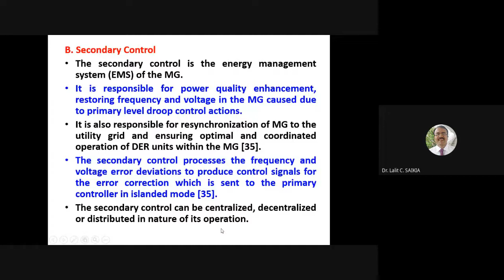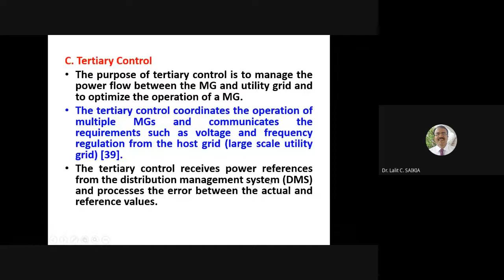Tertiary control's purpose is to manage the power flow between the microgrid and the utility grid - from microgrid to utility and utility to microgrid. Tertiary control coordinates the operation of multiple microgrids and communicates requirements such as voltage and frequency regulation from the large-scale utility grid. It receives power reference from the distribution management system and processes the error between the actual and the reference.